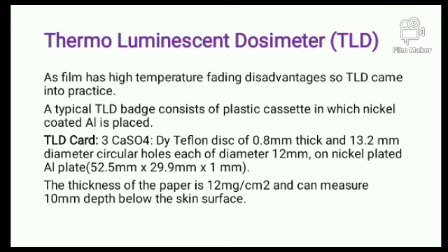And this is very much useful for measuring the doses of X-ray, beta, as well as gamma radiation also. So that is why we are saying the TLD badge is not only used for personal monitoring devices, it is also used in our radiotherapy areas to measure the amount of dose received by the eyes, and how much dose has penetrated the patient's body. So that is also helpful for them. Next thing is, till now there is no record that, due to huge climatic conditions, any fading of records has occurred. So that is very much useful for us also.